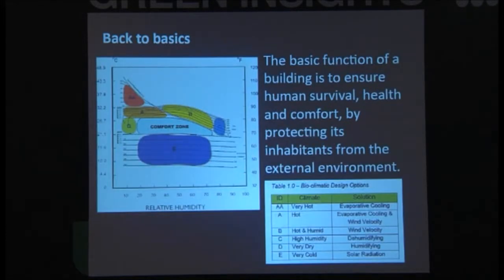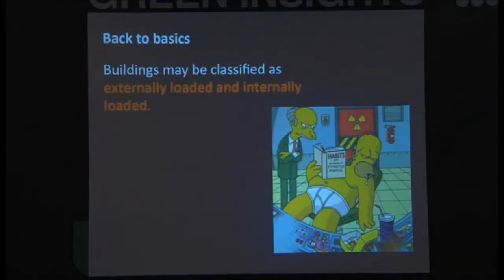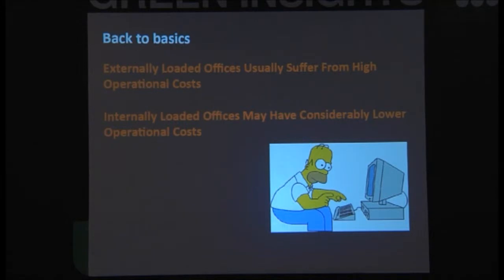What we're looking to do is provide a building where we're within the comfort zone. So buildings can be classified as externally loaded and internally loaded. Externally loaded offices usually suffer from high operational costs. Now in Malaysia we have externally loaded buildings because all the heat comes through the windows. We build big glass buildings and all that heat comes in and then we try to cool it. Internally loaded offices have considerably lower operating costs because then the heat is coming from the people, from the equipment that they're using.